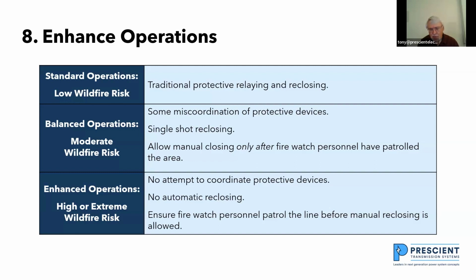If I'm looking at traditional protective relaying under standard operation, I might have an instantaneous relay set at 2,400 amps. Under balanced operations, I would reduce the set point of an instantaneous relay from 2,400 amps to 1,800 amps. 1,800 amps can overreach a recloser or something like that, but it won't reach to the end of the line, and that's okay. When I get extreme or high wildfire risks, I'm giving up coordination whatsoever. I'm not going to use automatic reclosing. I'm going to set my instantaneous relays as low as I can so that I have maximum sensitivity. So under traditional, I could set an instantaneous relay at 2,400 amps. In balanced operation, I give up some coordination and reset that relay at 1,800 amps. In enhanced operations, I'm going to reset the relay to 1,200 amps.